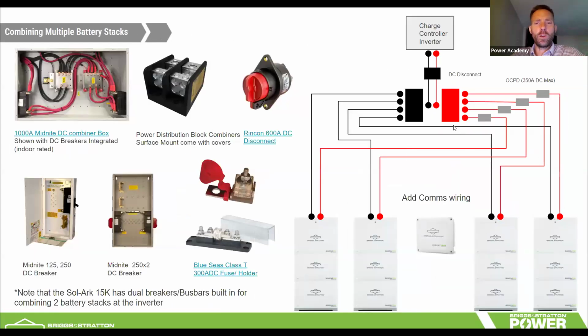So let's talk a little bit about multiple stacks. Let's suppose you wanted to do 4 stacks of batteries with a single inverter. If you're going to do more than 2 stacks, you will need to use a combiner, and there are a number of different ways to use one. This kind of messy looking diagram I've made on the right side of the screen is done in a specific way, and I'll talk about that in a second. When you are doing multiple stacks of batteries, you'll want each of the cable lengths to be the same. That makes sure the inverter is balancing the load equally among those 4 battery stacks.